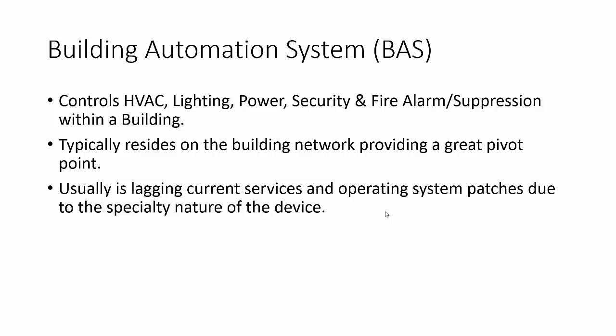What do I mean by that? Well, the building automation systems, what happens with them is when they're developed, they have so many different integration points between the different protocols that they're very heavily dependent on the frameworks and the code versions that they're developed in. For example, .NET, Java, etc. So if there's a patch for .NET or for Java or one of those, it oftentimes cannot be applied until the building automation system is put in a different, either a hot patch or a release and sent out to the customer. Because just going and applying that framework, first off, these are embedded OSs, so you really wouldn't have a way to apply the framework. Second off, even if you did, you may end up breaking something that's dependent on the framework in which this building automation system was developed.